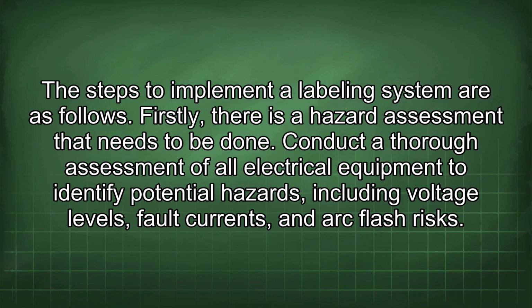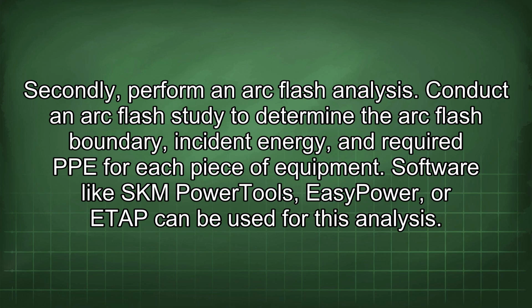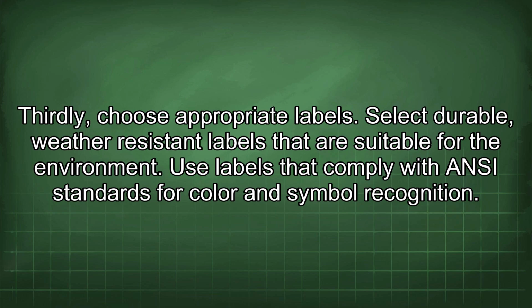Conduct a thorough assessment of all electrical equipment to identify potential hazards, including voltage levels, fault currents, and arc flash risks. Secondly, perform an arc flash analysis. Conduct an arc flash study to determine the arc flash boundary, incident energy, and required PPE for each piece of equipment. Software like SKM Power Tools, Easy Power, or ETAP can be used for this analysis. Thirdly, choose appropriate labels. Select durable, weather-resistant labels that are suitable for the environment. Use labels that comply with ANSI standards for color and symbol recognition.